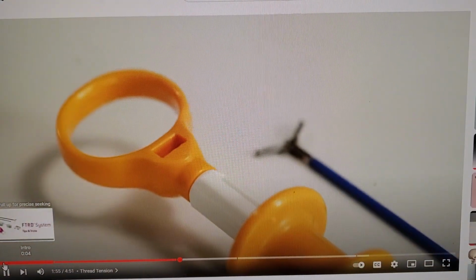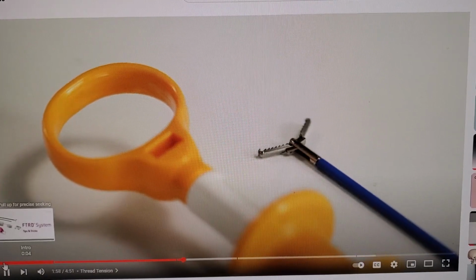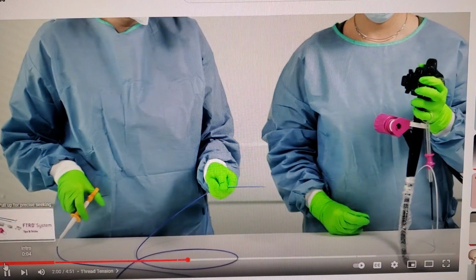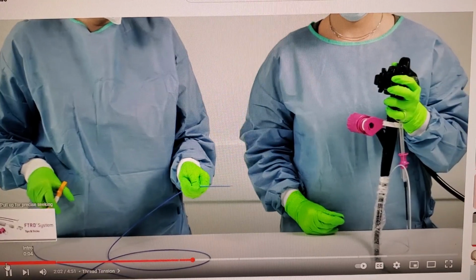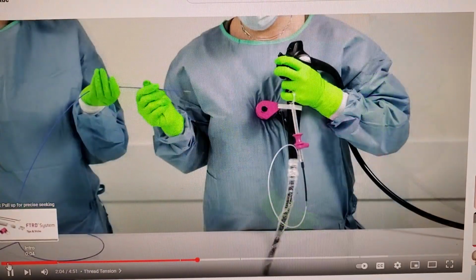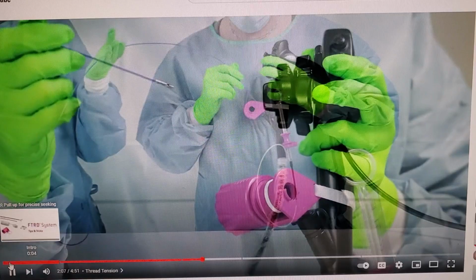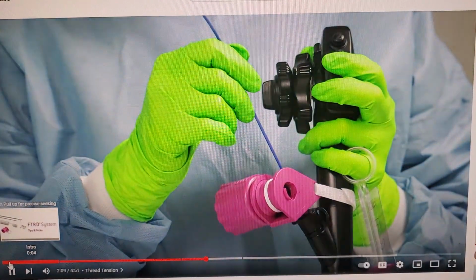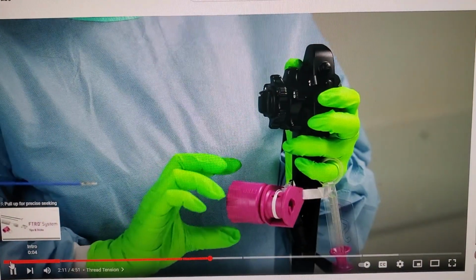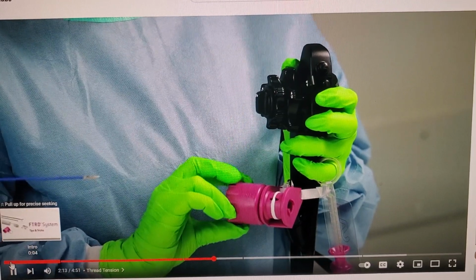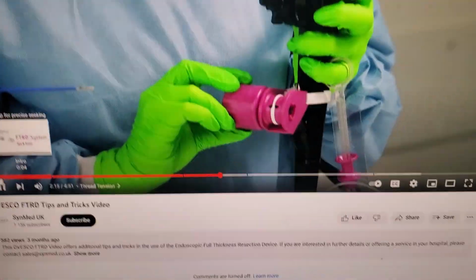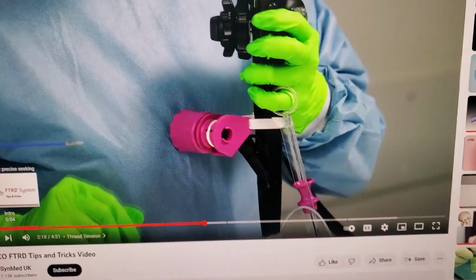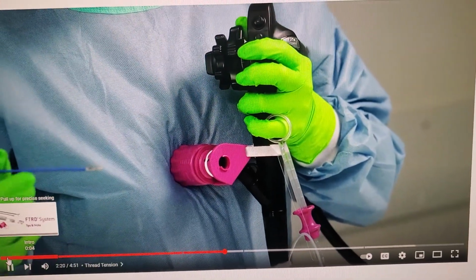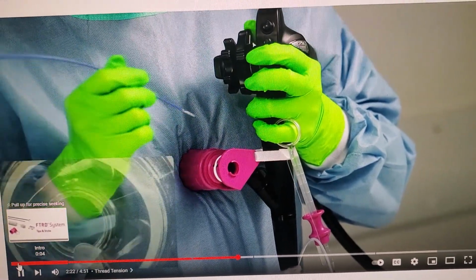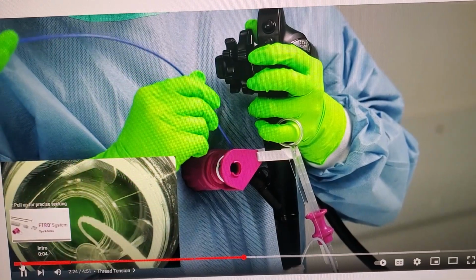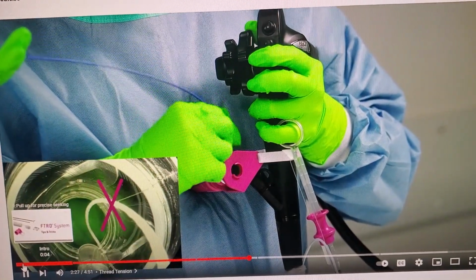While inserting the FTRD grasper into the working channel, it must be ensured that the thread remains slightly tensioned, otherwise it may wind itself around the instrument, making clip application difficult or even impossible. Therefore, the release thread should be wound up by turning the hand wheel clockwise until a slight tension can be felt. Should the thread become loose when inserting the grasper, the hand wheel can be pressed against the upper body to prevent the thread from unrolling or becoming slack.